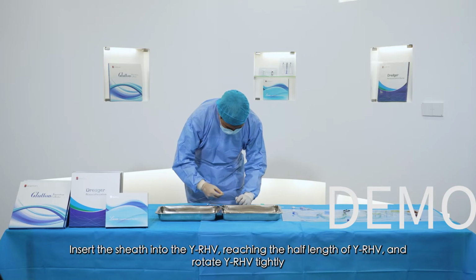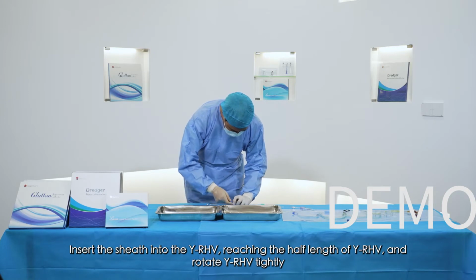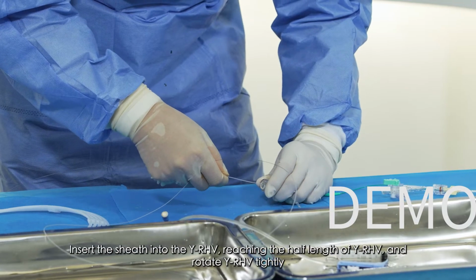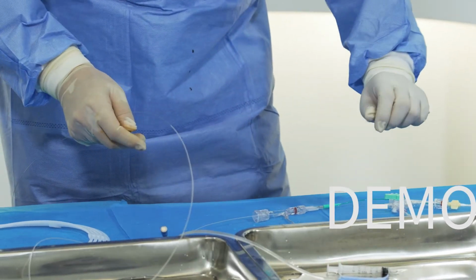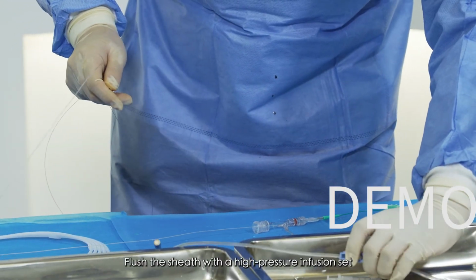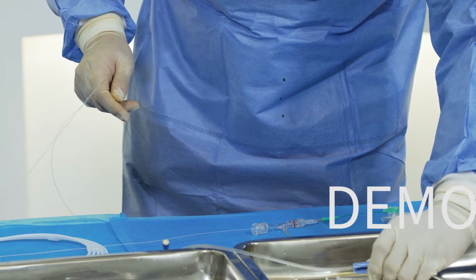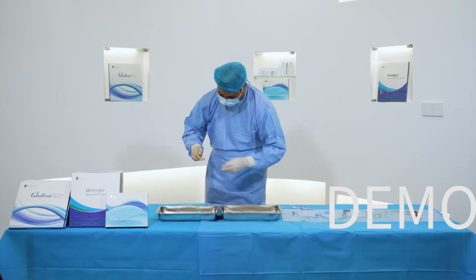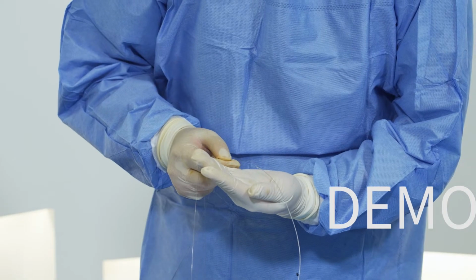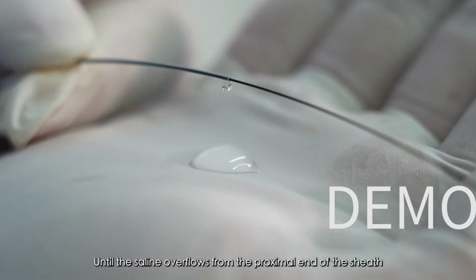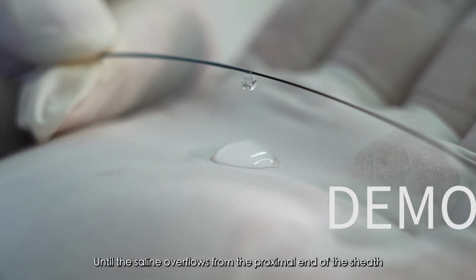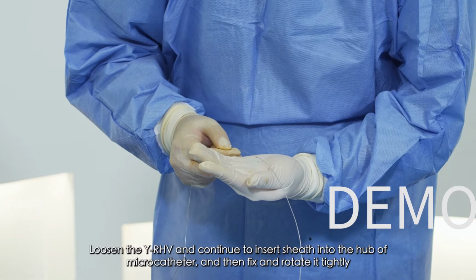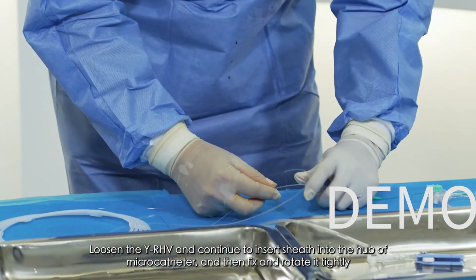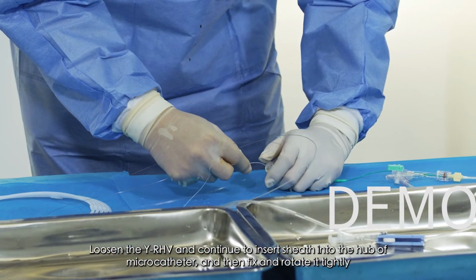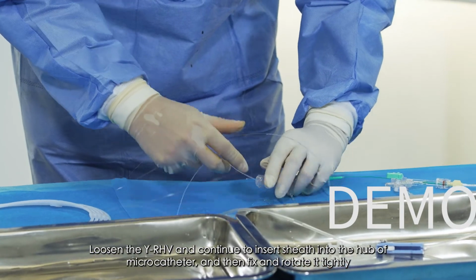Insert the sheath into the YRHV, reaching half the length of the YRHV, and rotate the YRHV tightly. Flush the sheath with a high-pressure infusion set until the saline overflows from the proximal end of the sheath. Loosen the YRHV and continue to insert the sheath into the hub of the microcatheter, then fix and rotate it tightly.